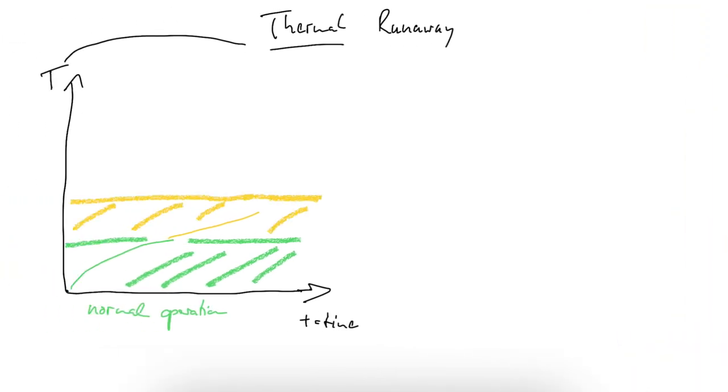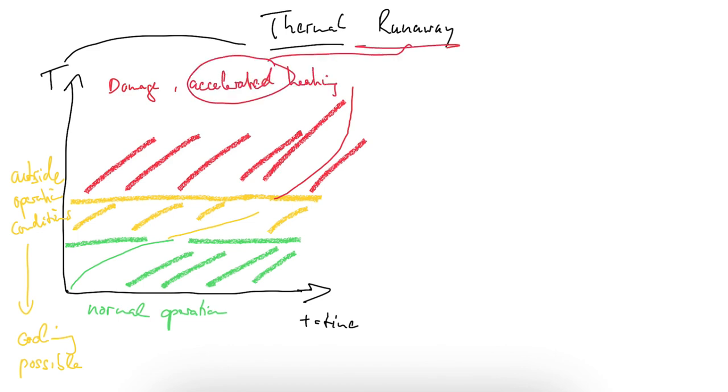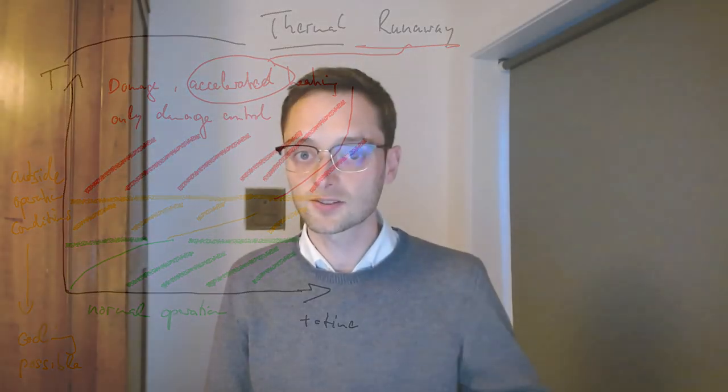The question is of course what makes a thermal runaway start, and there we have basically a lot of reasons. At the top level: first, heat is generated from some reaction or some external effect — for example, the connection or bond to the cell is not well enough, and then you have a high resistance there. When you charge and discharge you generate a lot of heat at this resistance point, at this bond. Or it can also be internal — there is really some manufacturing defect and that leads to some reaction that generates heat while operating the cell.